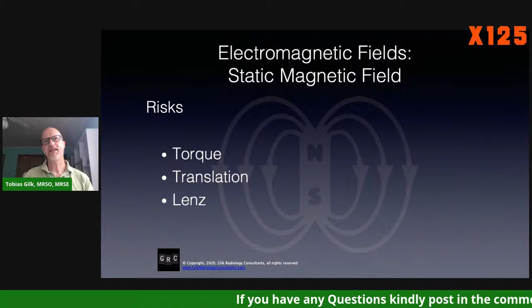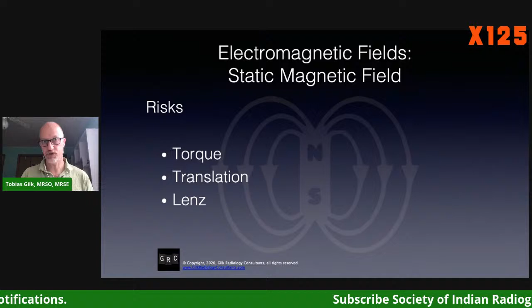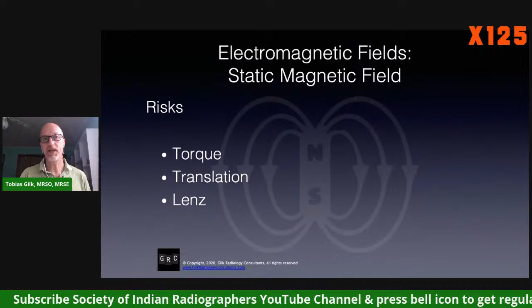And then the Lenz effect. Lenz effect is a function of Faraday's law of induction, which actually does, in some instances, the reverse of what translation does. The Lenz effect actually retards, slows, prevents motion towards the magnetic field. And that's caused by a different set of criteria or influenced by a different set of criteria than is translation and different than torque. But it's an important safety factor that we need to be aware of when we're bringing patients with implants, devices, or even just objects or materials close to the MRI scanner.